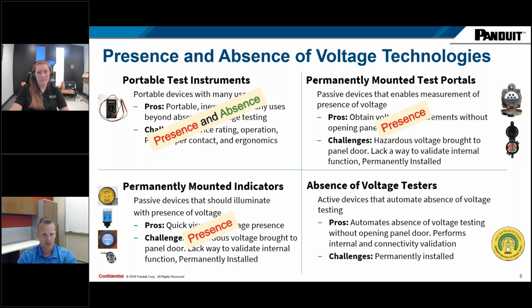And then come absence of voltage testers. It's an active device that automates the absence of voltage testing process. So you don't have to open the panel door. That device is installed in the panel. We'll get more into that, I think, in the next slide. It's installed in the panel door. Don't have to open the door at all, and it performs internal and connectivity validation steps every time you push a button and initiate the test. It will verify that its own internal workings are performing properly, as well as that it's still connected to the voltage source. Challenges, it's permanently installed. So if you do typically test for the absence of voltage in a few different spots within a cabinet, you do need to install an absence of voltage tester at each discrete location.